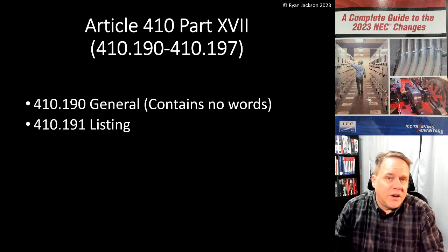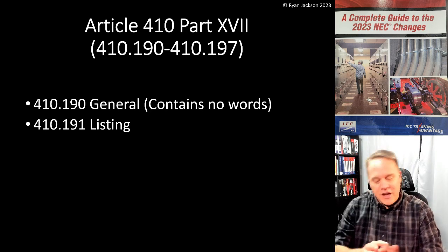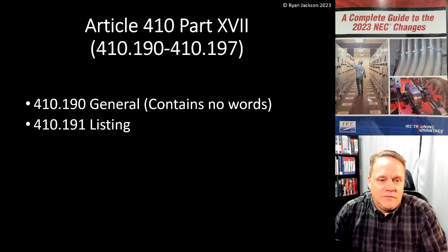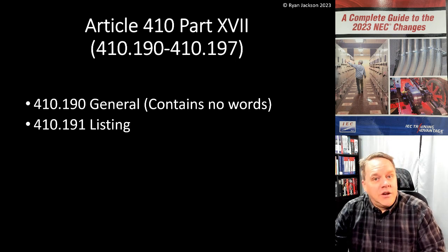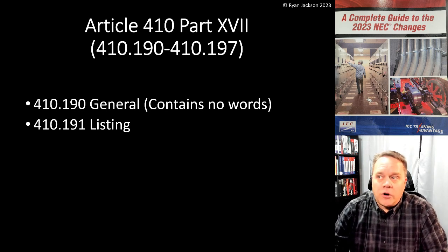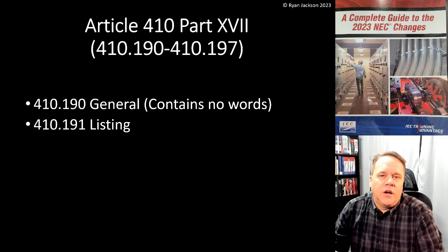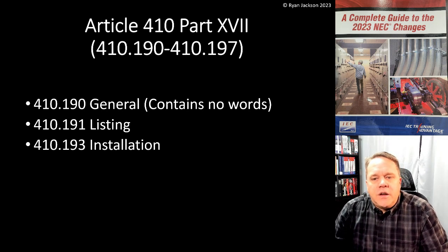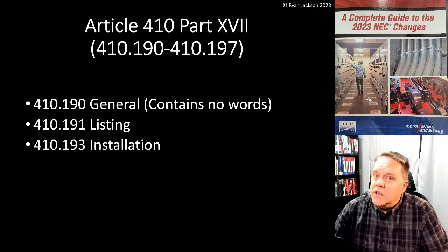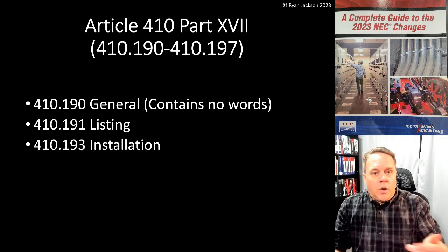Section 410.190 is labeled 'General' but literally has no words in it. Section 410.191 on listing just says germicidal irradiation luminaires have to be listed — which is already covered by 410.6. Section 410.193 basically just says to follow installation instructions, which is already required by 110.3(B) for listed products.